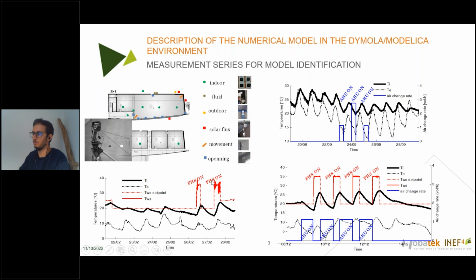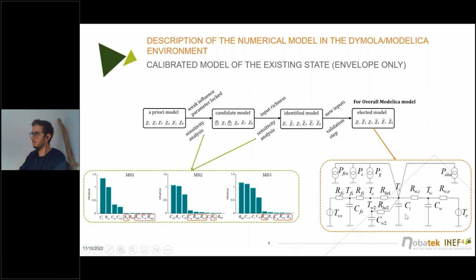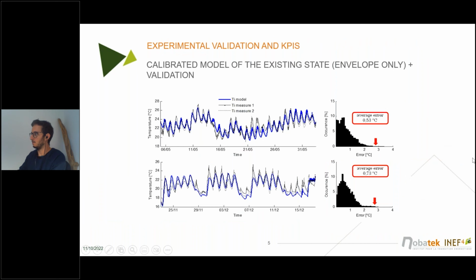So we force the heating. In this one, at night we make some cooling, and during the day some heating. And in this one, there is only cooling. So it's some forced tests. And after we use this data for the next step, to calibrate or identify the parameters of the model.